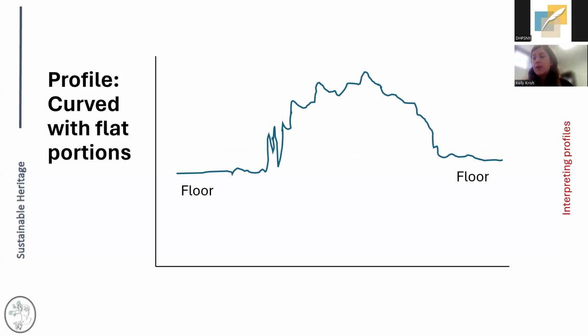Within that, there's three variations. So this one I want to show, if you imagine that those two ends where it's more flat, if that's kind of your winter time, and then that middle bit is summer again, you can see it has what we would call a dew point floor. And so the floor essentially acts just like a normal floor. And even though we know from the outside air curves that we looked at that moisture levels are dropping in the winter, our system's working, and it's not letting the moisture go below a certain point.